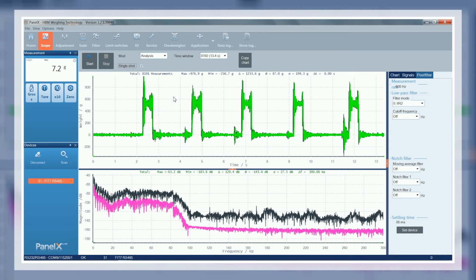We will now begin optimizing the electronic processing of the raw signal. The electronic array of the FIT-7A includes several electronic filters, which can be adapted to the mechanical structure, the product to be weighed, and the relevant environment. These filter settings are mapped in Panel X and can be optimized to suppress noise and interference on the basis of the test measurement data. The filter settings determined here are then forwarded to FIT-7A. Multiple filter settings can be stored on a laptop, which allows you to switch between the various settings as needed.